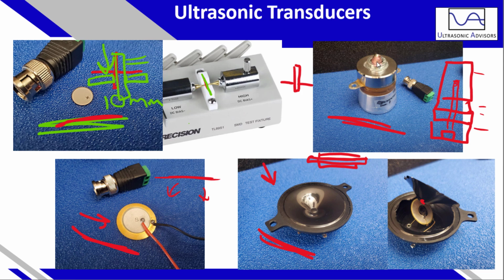If you see, there's this little bolt stuck in here, and I actually left that in there by accident. But this little bolt or nut actually comes out if you can pry it out, and it goes on the other side of the transducer, which helps to use it for mounting to a plate or a container that contains the water for the ultrasonic cleaning. But I left it in there, and that condition of having this odd-shaped piece jammed in the bolt there is what caused the spurious mode. So I've removed that.